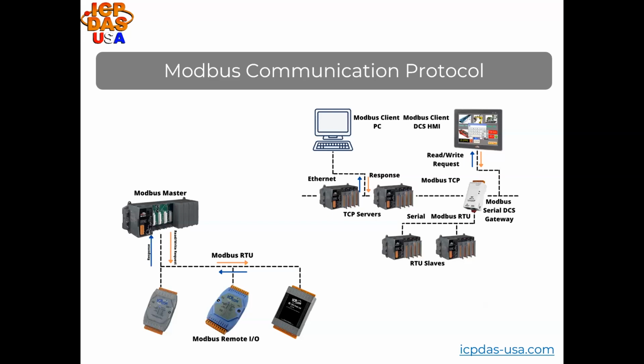Our WinPAC and touchpad controllers are often used as Modbus masters. Our Modbus RTU I/O modules and rack-based data acquisition systems are Modbus slaves. Modbus RTU is transmitted over serial lines like RS-232 or RS-485. Modbus TCP communicates over Ethernet cabling.